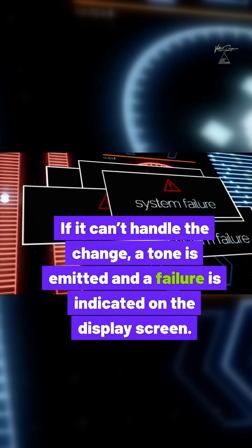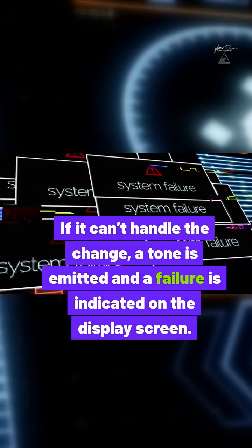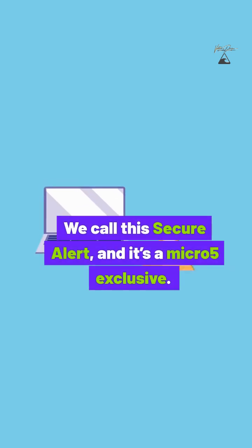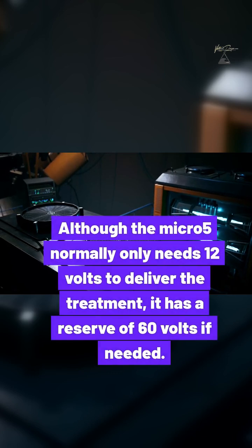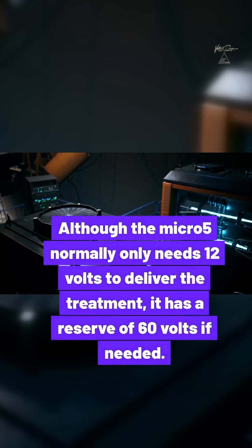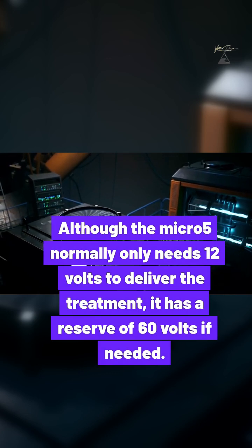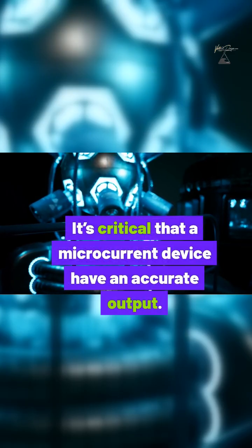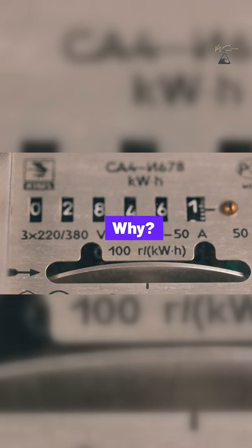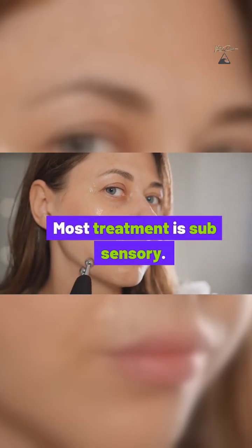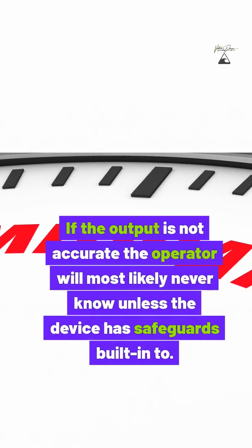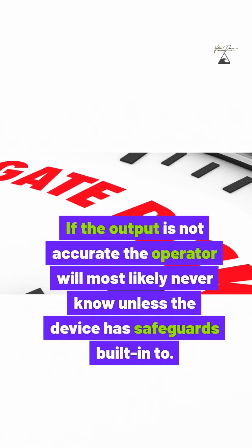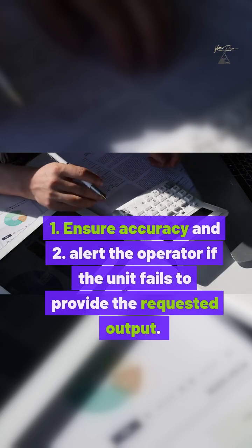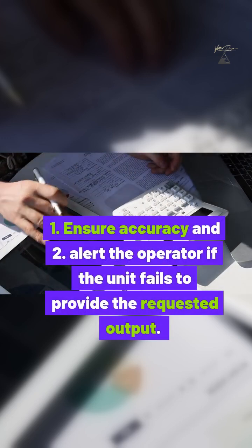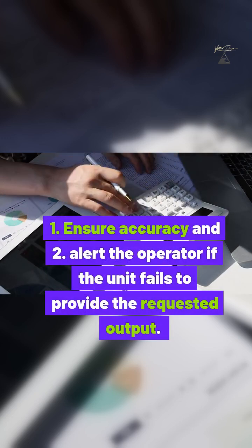If it can't handle the change, a tone is emitted and a failure is indicated on the display screen. We call this Secure Alert, and it's a Micro5 exclusive. Although the Micro5 normally only needs 12 volts to deliver the treatment, it has a reserve of 60 volts if needed. It's critical that a microcurrent device have an accurate output. Why? Most treatment is sub-sensory. If the output is not accurate, the operator will most likely never know unless the device has safeguards built in. 1. Ensure accuracy, and 2. Alert the operator if the unit fails to provide the requested output.